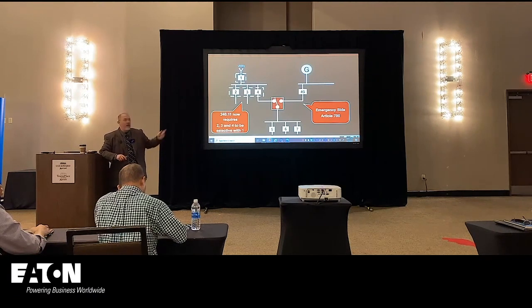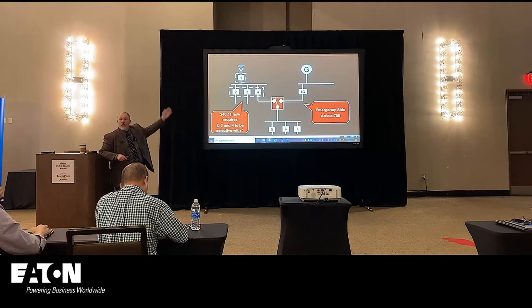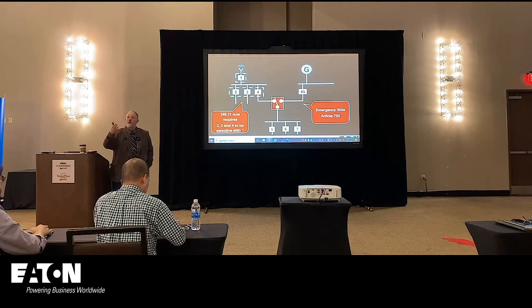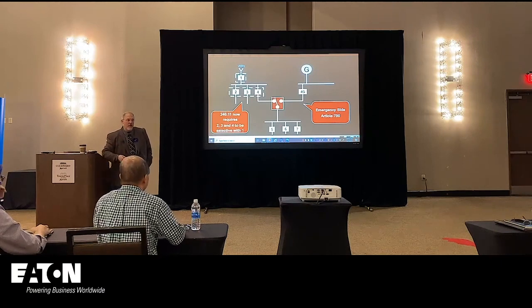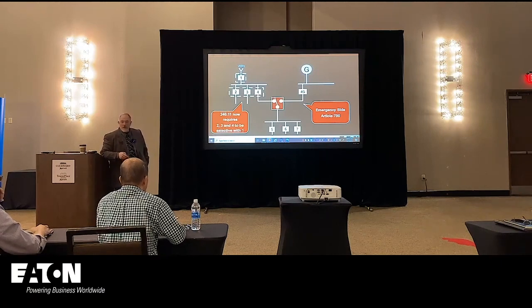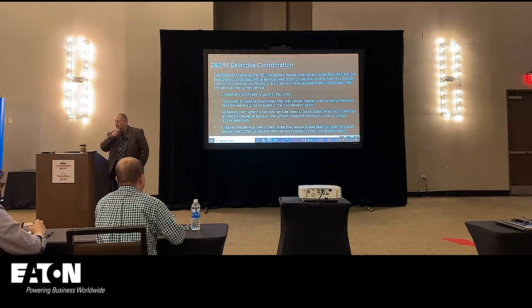So everything in that top left. You don't have to selectively coordinate down below 2 or down below 3, but you know that if you have a fault down below 2, you'll take out 2 and you won't transfer. If they did not selectively coordinate, you could take device 1 out, which is your main, and now you've forced a transfer needlessly. And what if the transfer doesn't switch? What if the generator doesn't start? Now you're into an emergency mode. So that was the point there.